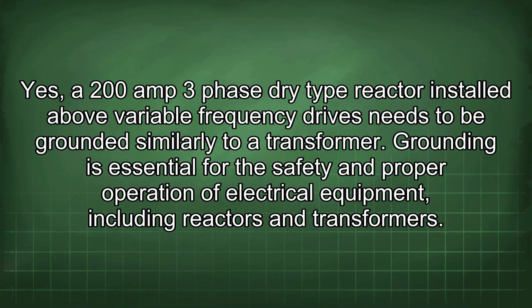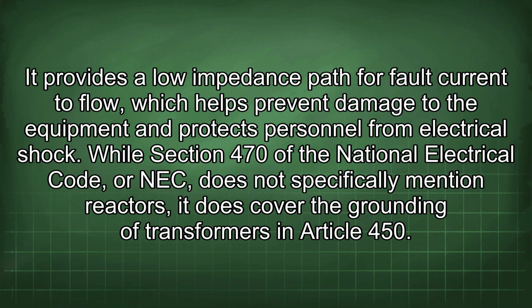Yes, a 200 amp 3-phase dry-type reactor installed above variable frequency drives needs to be grounded similarly to a transformer. Grounding is essential for the safety and proper operation of electrical equipment, including reactors and transformers. It provides a low impedance path for fault current to flow, which helps prevent damage to the equipment and protects personnel from electrical shock.